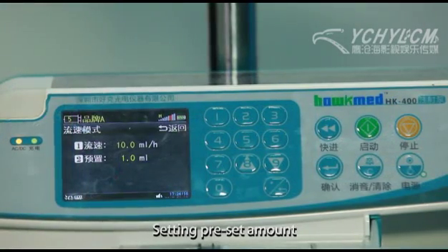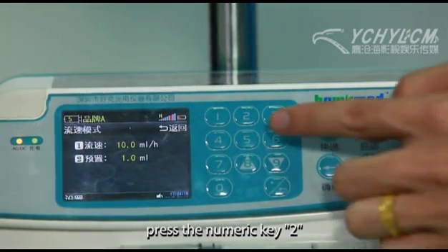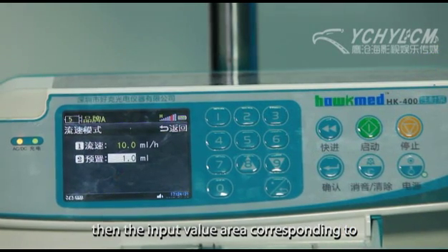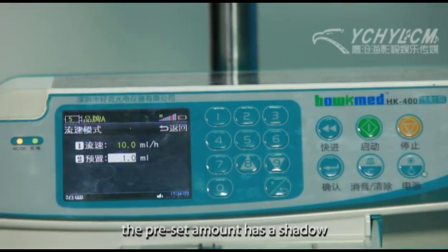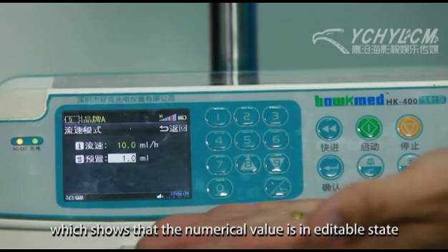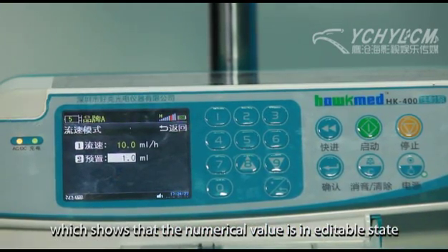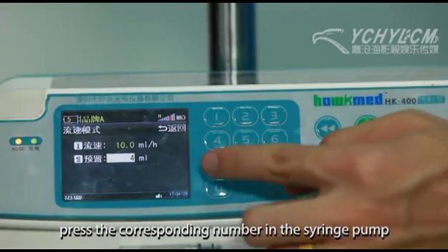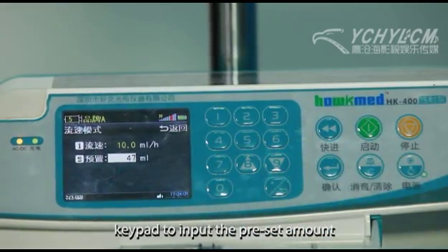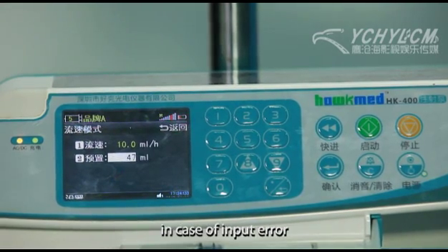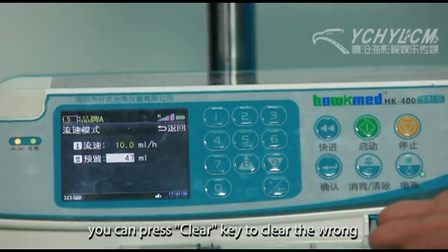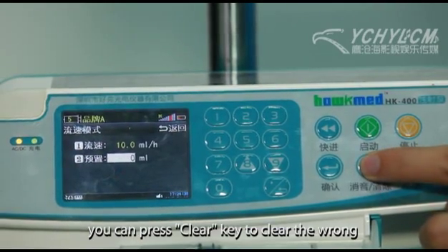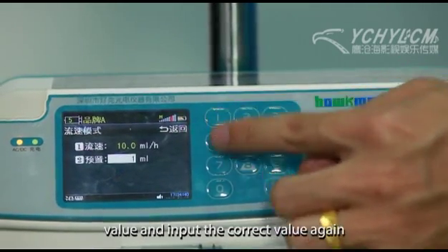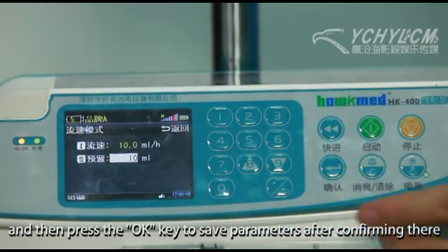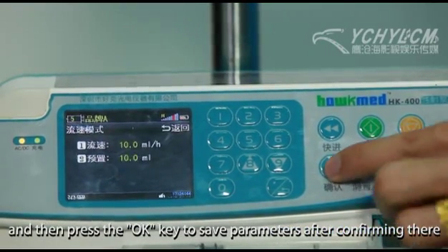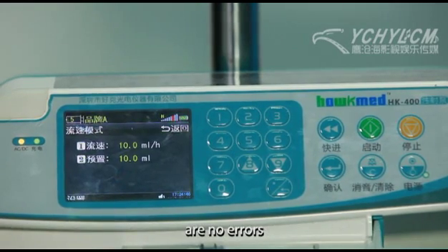Setting preset amount. Press the numeric key 2, then the input value area corresponding to the preset amount has a shadow, which shows that the numerical value is in editable state. Press the corresponding number on the syringe pump keypad to input the preset amount. In case of input error, you can press the Clear key to clear the wrong value and input the correct value again, and then press the OK key to save parameters after confirming there are no errors.